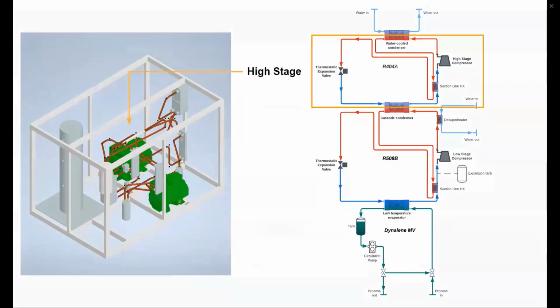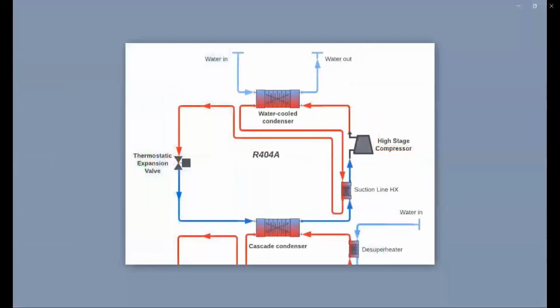First, looking at the high stage, key additions include the water cooling of the condenser, which allows for lower condensing temperatures and improved efficiency. Additionally, a suction line heat exchanger was added to optimize the values of superheat and subcooling.